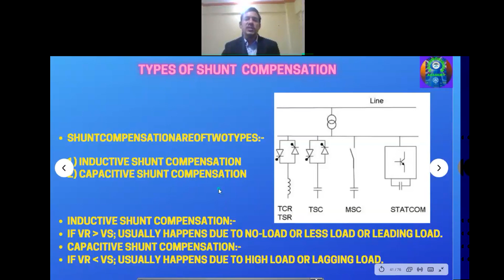For capacitive shunt compensation, when receiving end voltage is less than sending end voltage, then we go for capacitive shunt compensation. These are some of the shunt compensators we use in the power system. A very popular one is the STATCOM. STATCOM may be used with energy storage. So some combinations of the STATCOM are possible.